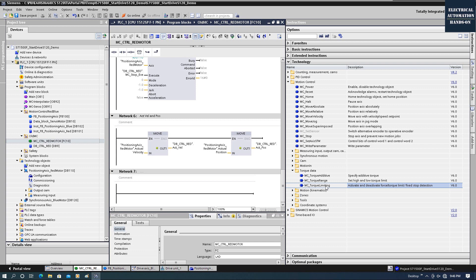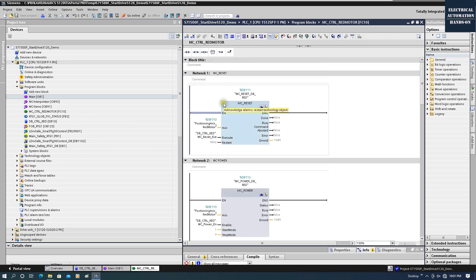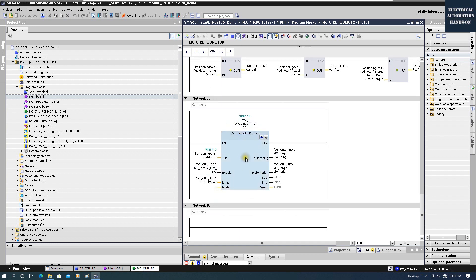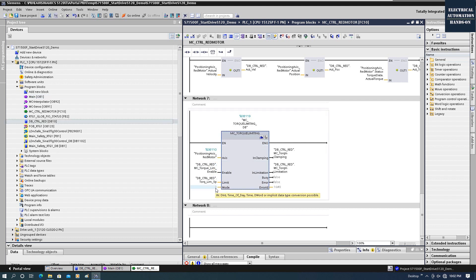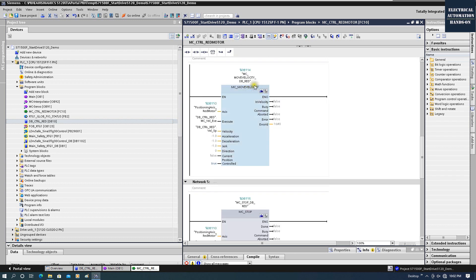Now let's download to the S120 and S7-1500 PLC and do the online test. We drag MC_TorqueLimiting from the library. The axis input should come from the motor axis — drag the TO DB directly there. This enable can be always on; while enable is on, we can change the limiting value on the fly. Additionally, we need to program MC_MoveVelocity because MC_TorqueLimiting only limits the torque — to control the motor running, we still need MC_MoveVelocity.